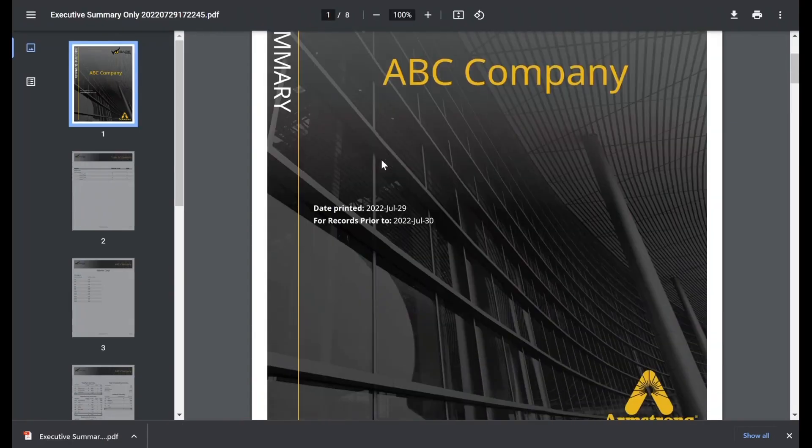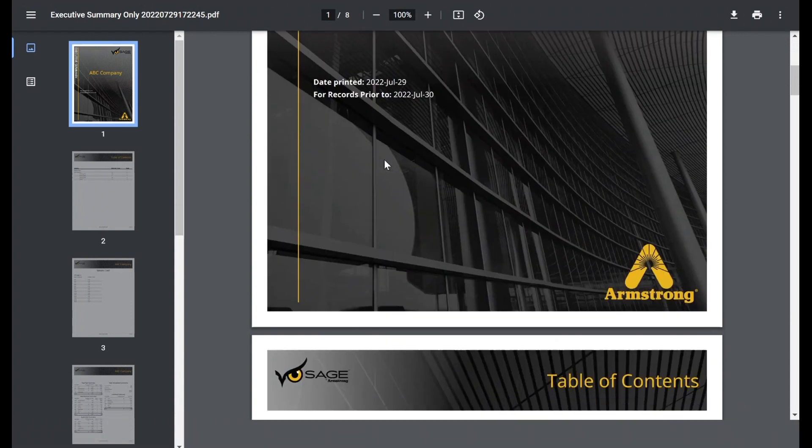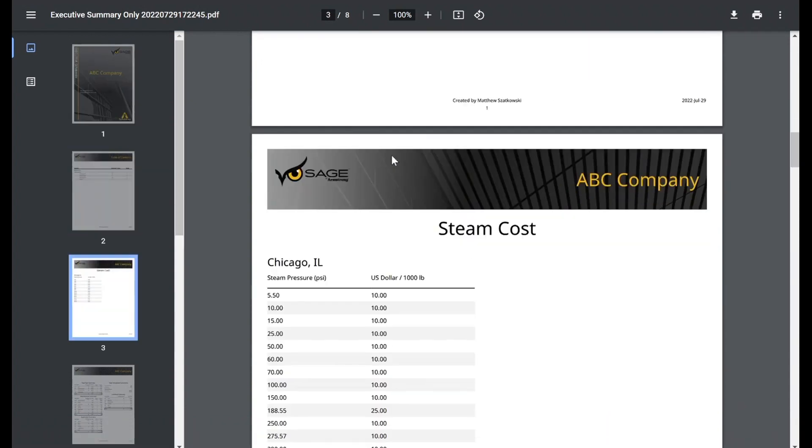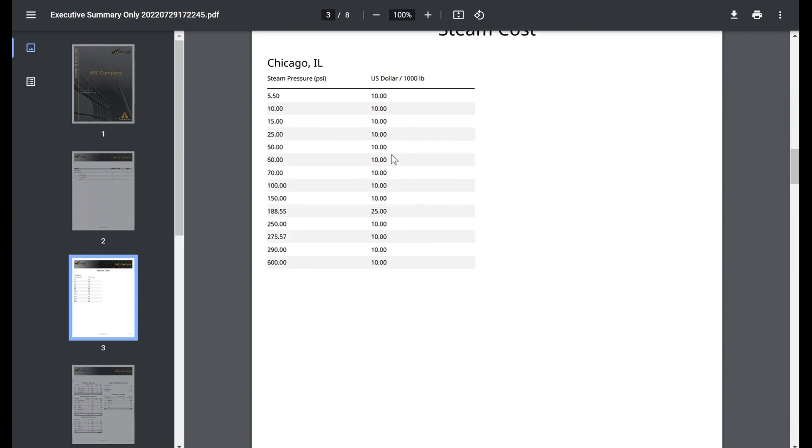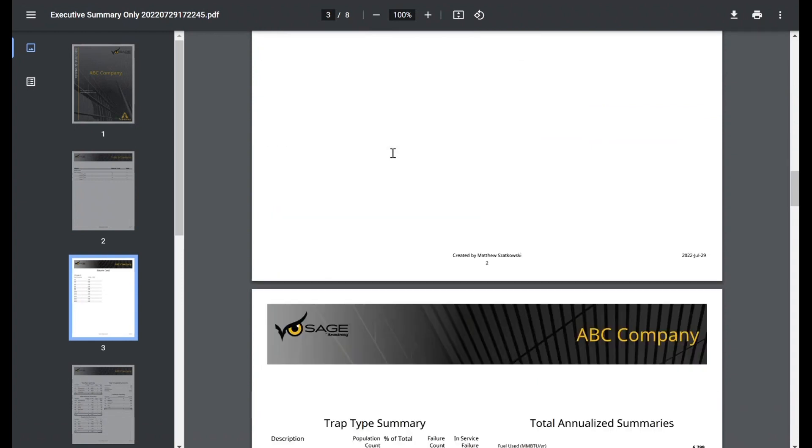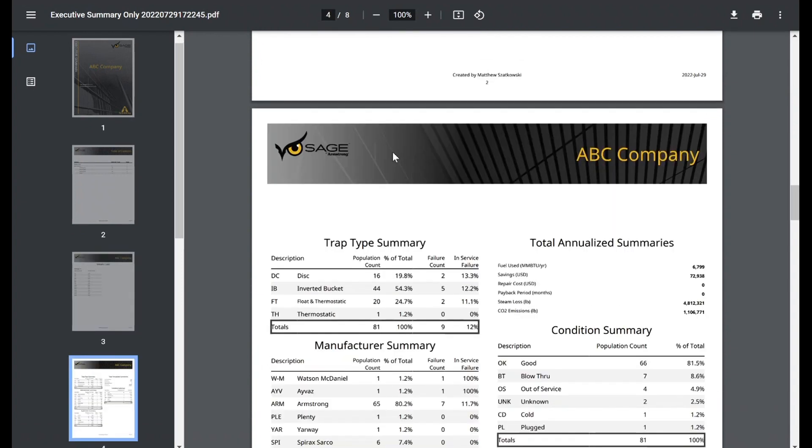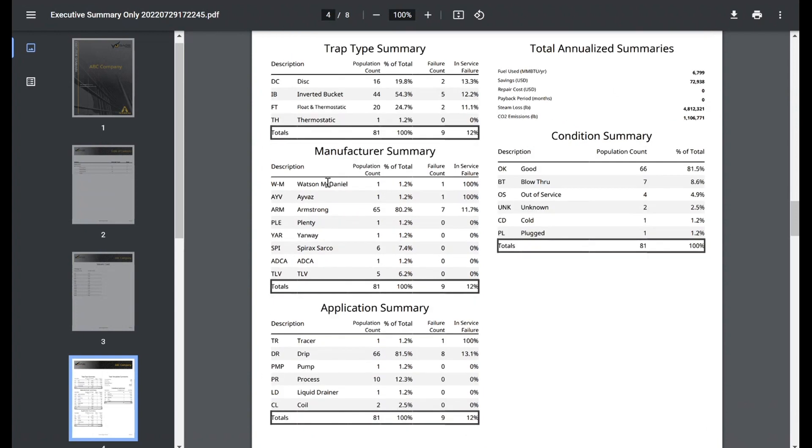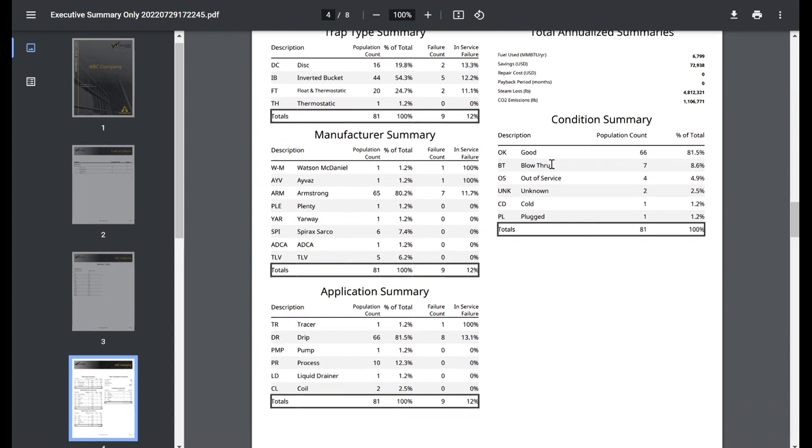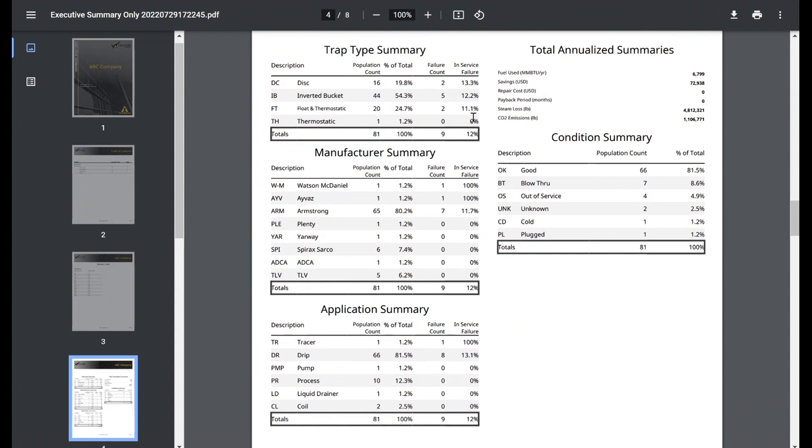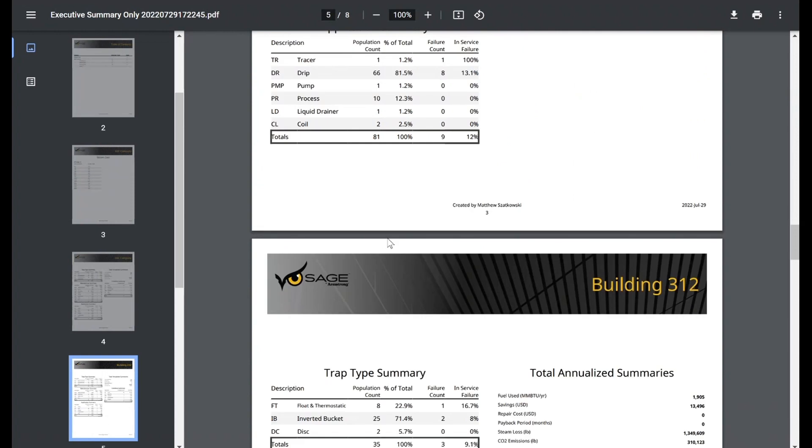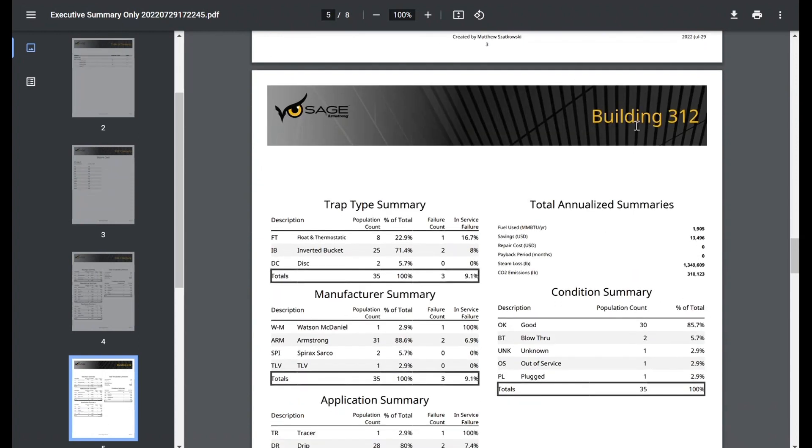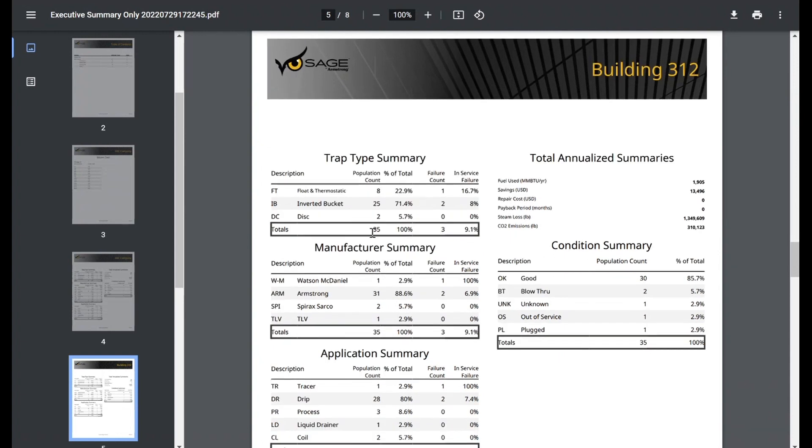You can see each one of our reports is generated with a title page, table of contents, and then the data from this specific report. The executive summary is looking at that high level overview of the population. So again, I ran this on just the Chicago location. So we're looking at 81 traps. What is the trap type makeup? How many of them are disks, inverted buckets? How many of those are in a failed state? How many of the trap population are Watson McDaniels or Armstrong? How many of those are in a failed state? What is our condition summary? Our annualized summaries are right here. It's giving us a high level overview of our population.